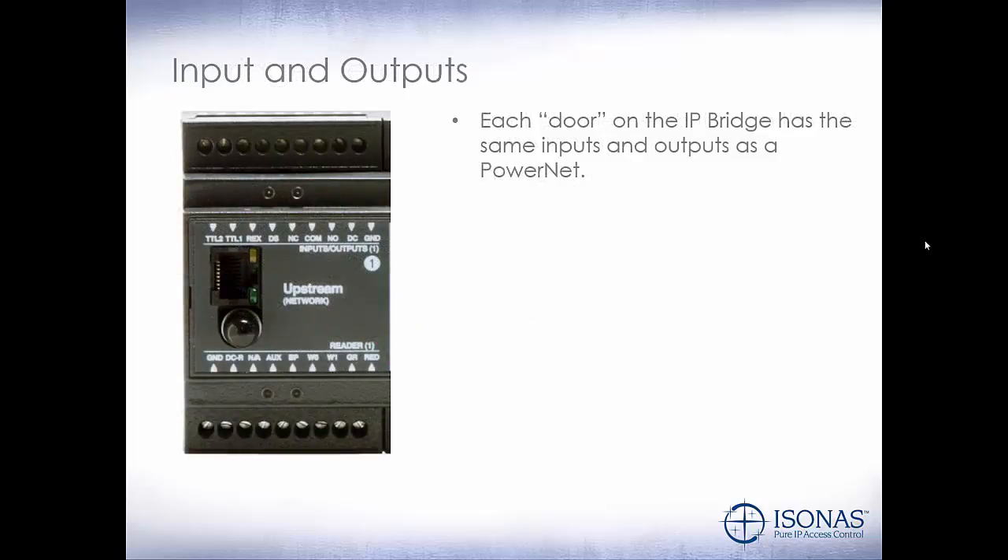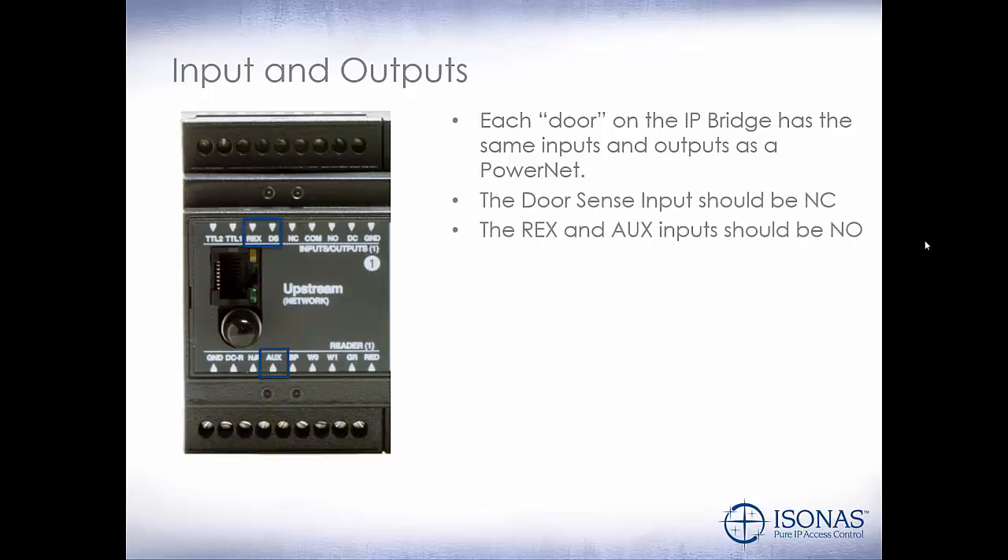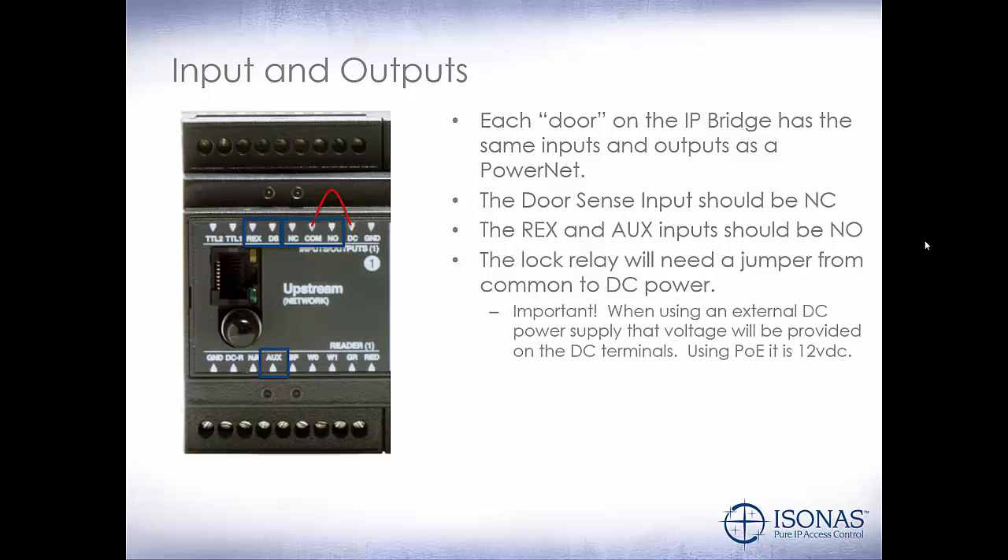Each door on the IP bridge has the same inputs and outputs as a PowerNet. You have a door sense input that should be normally closed, and you have REX and auxiliary inputs that should be normally open. The lock relay will need a jumper from the common to the DC power, as shown there by the red line. Important: when using an external DC power supply, that voltage will be provided on the DC terminals. So if you use a 24-volt DC power supply, you will have 24-volt DC on your DC and ground terminals at the top. When using PoE, it's always 12-volt DC.